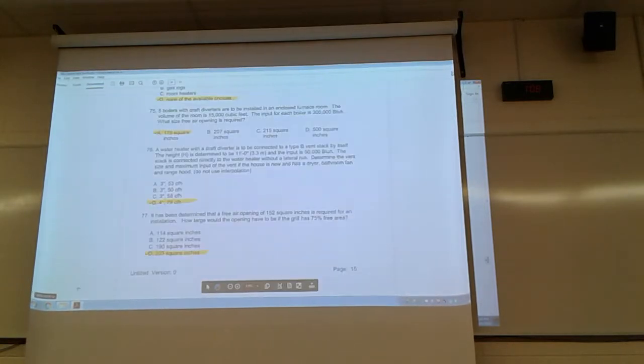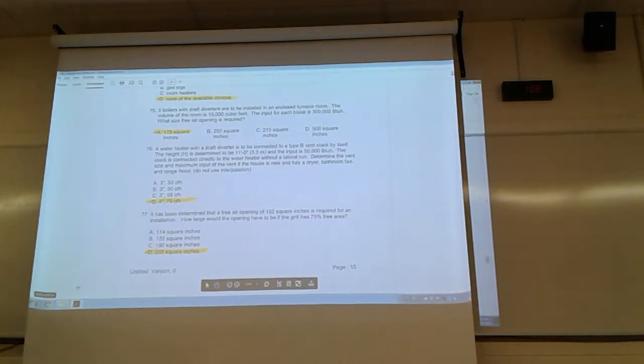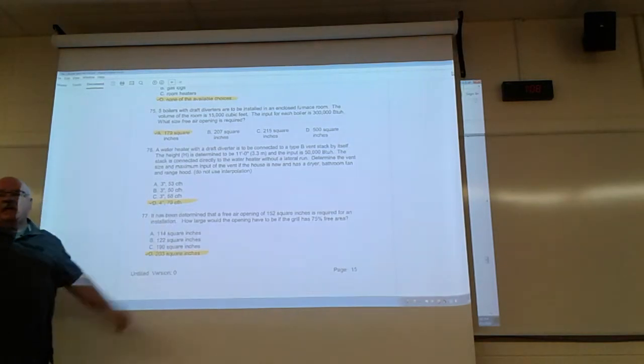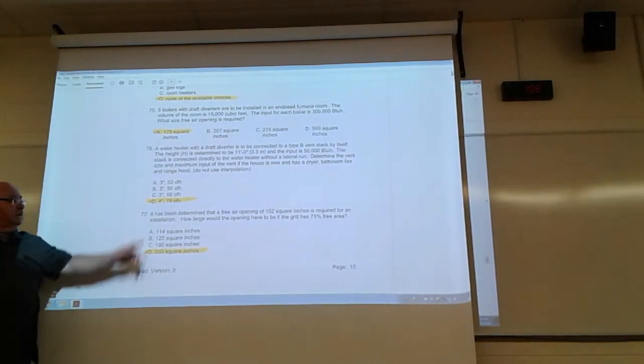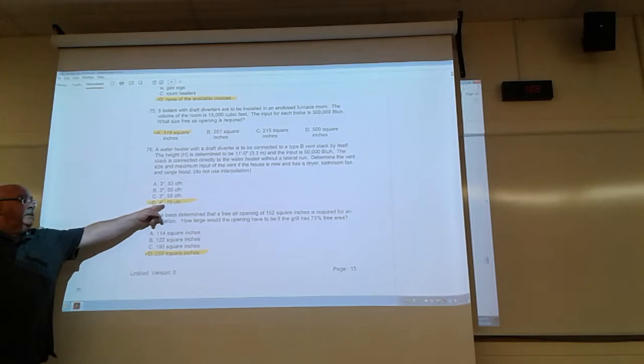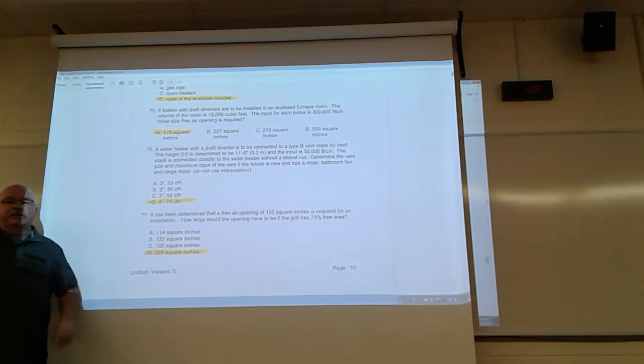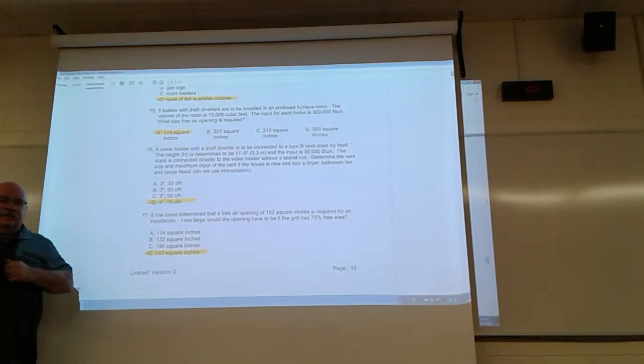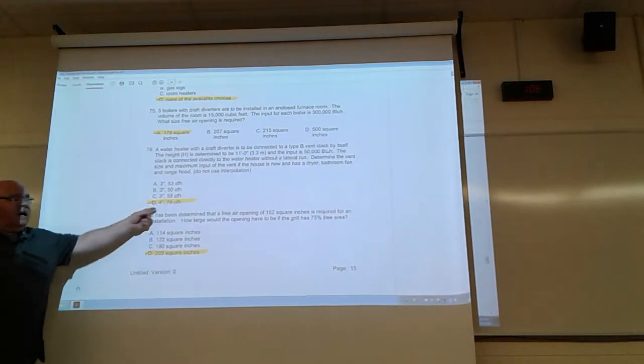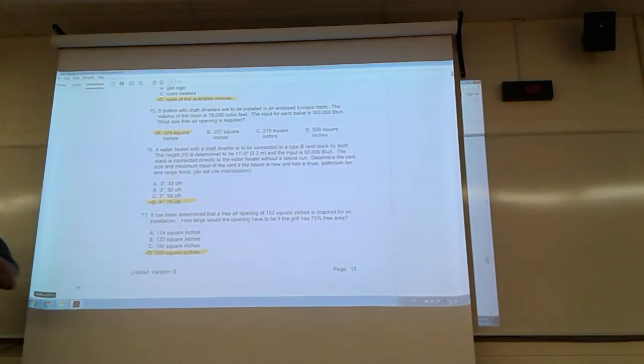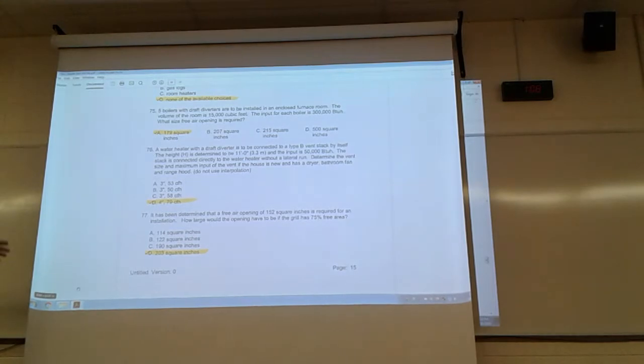Cubic feet an hour didn't matter. Okay, so 4 inches. CFH, what's CFH stand for? Cubic feet per hour? So they say 79 cubic feet per hour, well, they're talking about 79,000 BTUs. Okay, so be careful, I have seen that question on the test. Just like the oil, TSSA has a test bank of over 1,000 questions. This is just a sampling of 100. Okay, random sampling of 100, so they can mix and match whatever they want.